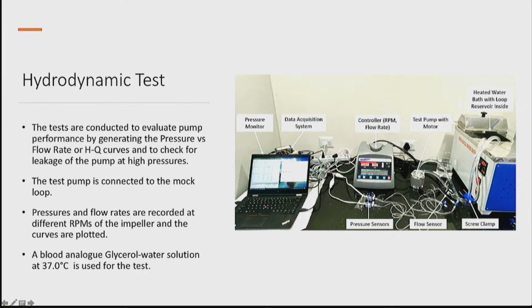This is the test setup at AIG Hospital for the hydrodynamic testing. Hydrodynamic testing is basically used to check the pump performance. Here we make the HQ curves, or the pressure versus flow rate curves, for the pump. Only after we get satisfactory HQ curves do we proceed with the biocompatibility testing. In this image, you can see the heating water bath in which the reservoir is placed. We are mimicking the human blood circulatory system here, therefore we are maintaining the temperature at 37 degrees centigrade.